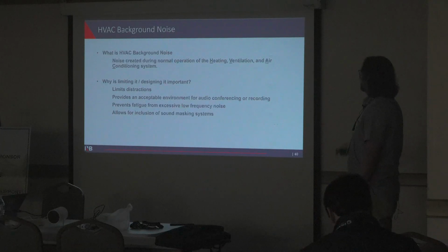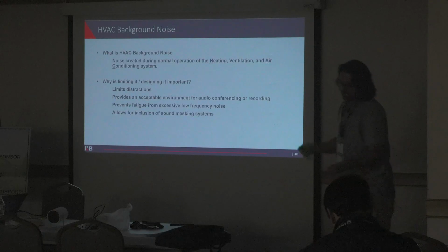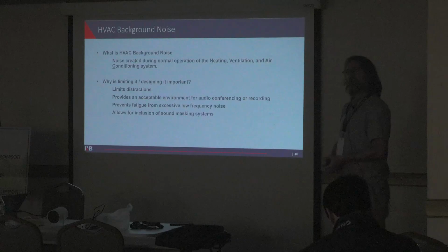Why do we track HVAC and building background noise? It limits distractions, provides an acceptable environment for audio conferencing, prevents fatigue, and allows for the inclusion of sound masking. Sound masking has been around a while, and some people say we don't need it, we'll just pick a tighter diffuser or make a noisier mechanical system. We don't recommend that, because it's out of your control. If you downsize your diffusers to get more noise and then find it's too loud on day one, you can't turn it down. But if you put in a sound masking system at 40 dBA and users say it's too loud, you can turn that down. So there's a bit of control there.